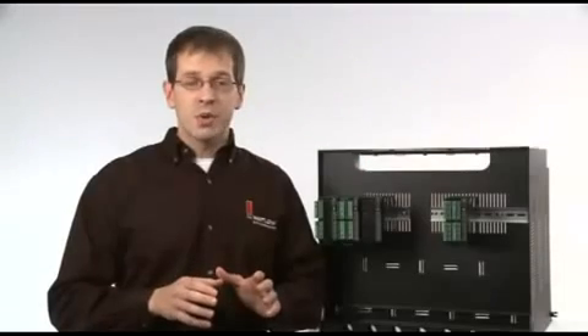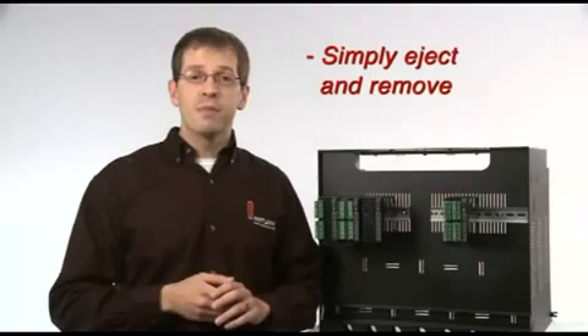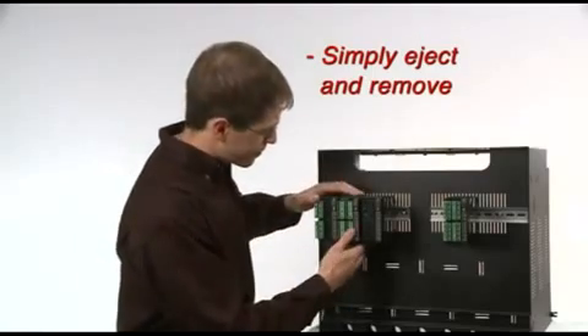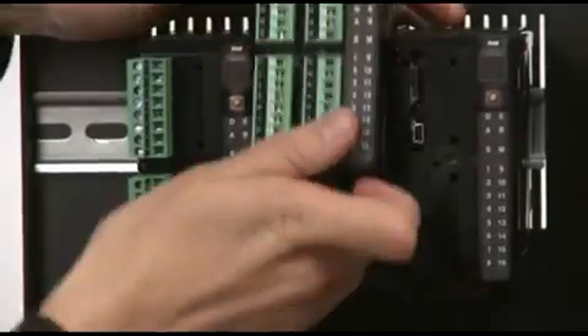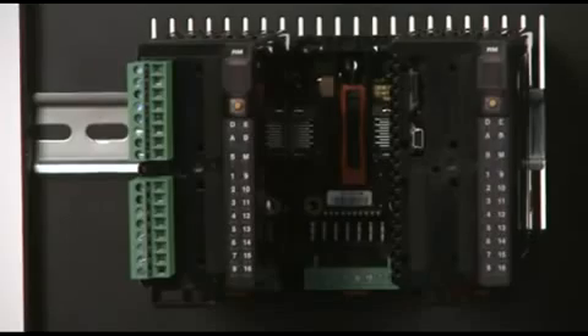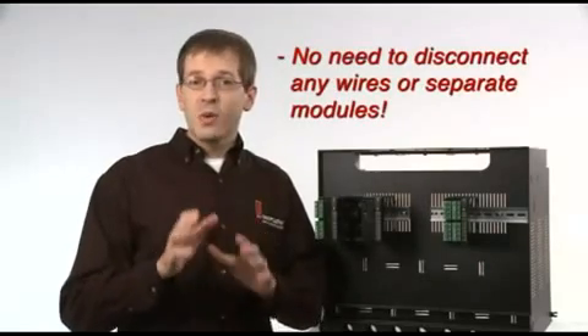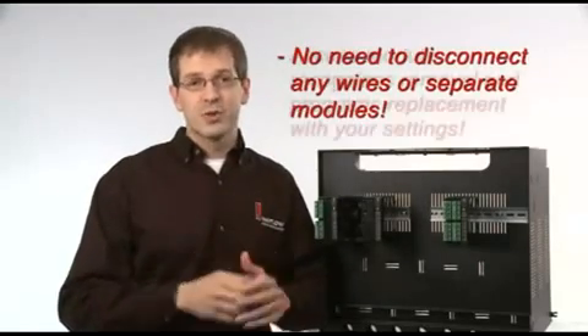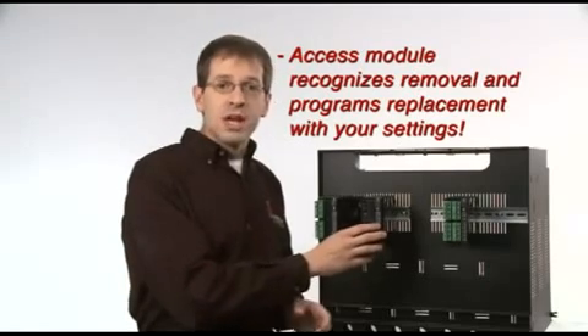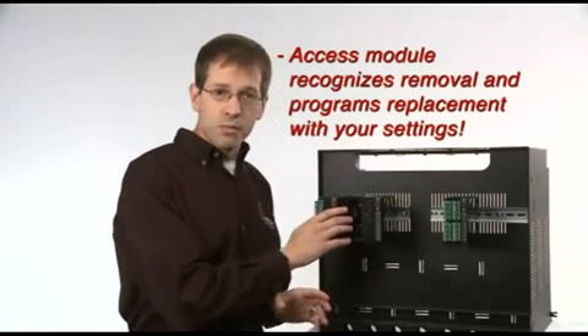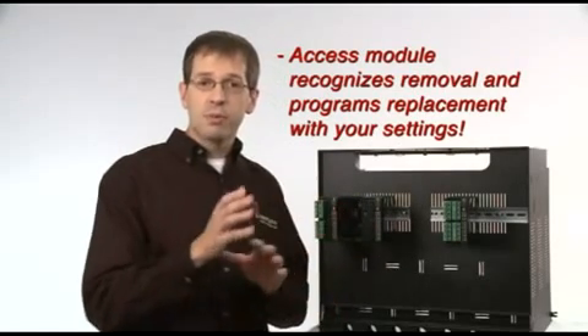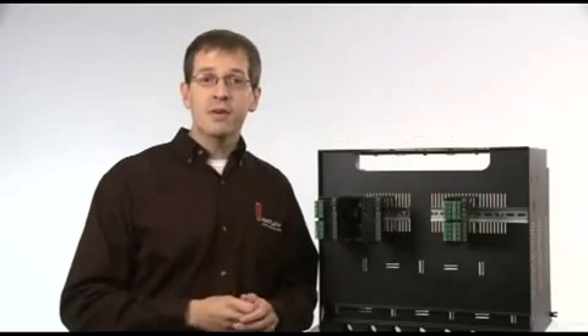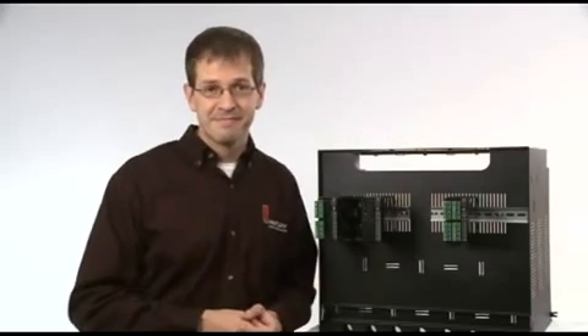Now, if you ever need to remove the module, simply eject it from the back plane and remove. There's no need to disconnect any wires or separate any modules. If you have an access module, it'll recognize the removal of the old module and automatically program the replacement with your settings or give you the option to create new ones.